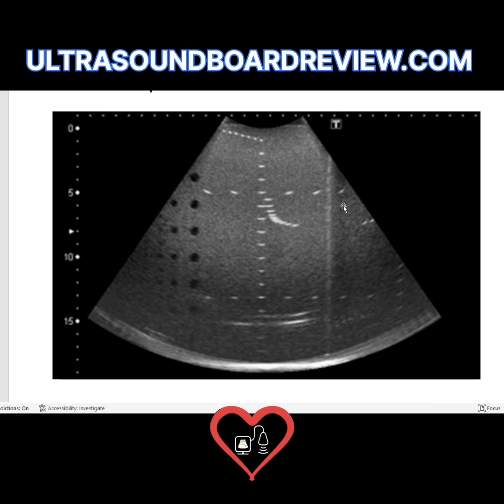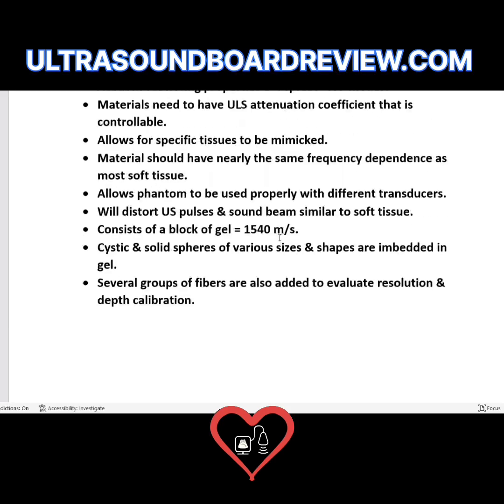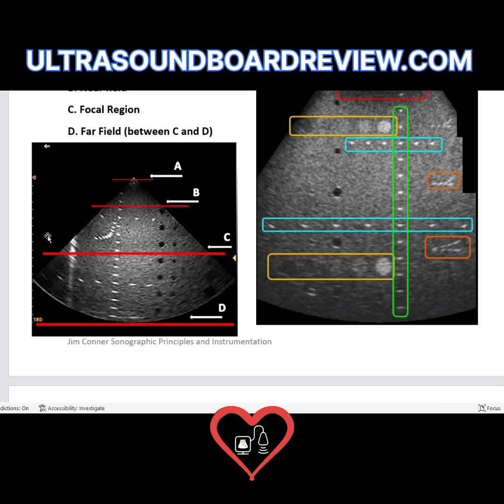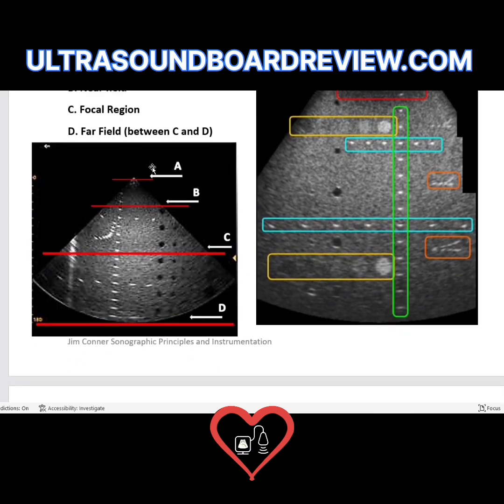Looking at this image: the blue calibrates the depth, the white calibrates the dead zone, the yellow has the best axial resolution, and the pink calibrates the dynamic range. On your boards, they'll either ask questions like these or show the phantom labeled A, B, C, D and ask which area represents the dead zone — you would select A. Which one represents the near field? B. Which one represents the Fraunhofer zone? D. They may ask you to click on the area that represents the dead zone.